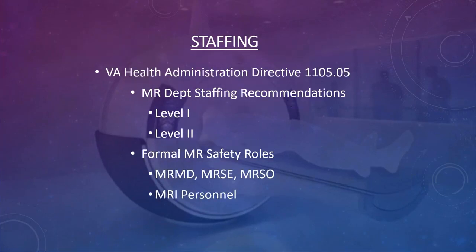The ACR bases their staffing on the VA Health Administration Directive from 2008, Directive number 1105.05. This discusses the staffing needed to efficiently run an MRI department, covers level one and level two staffing, and specifies that if your department has one magnet, you should have two people at all times whenever there is a patient or volunteer in the magnet.